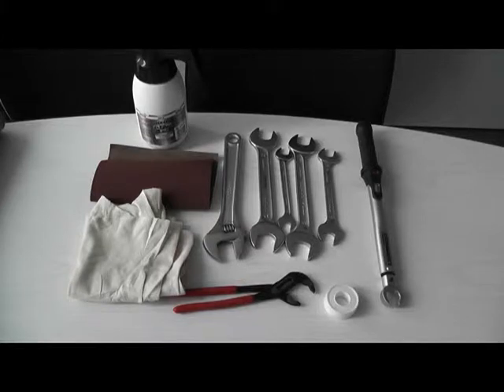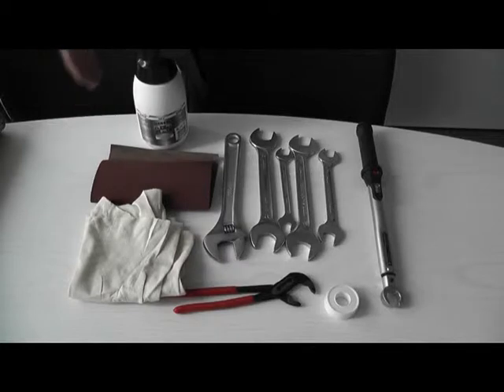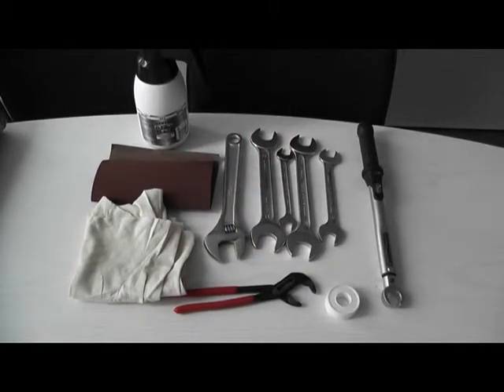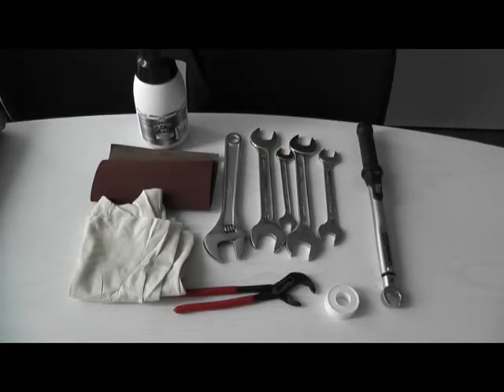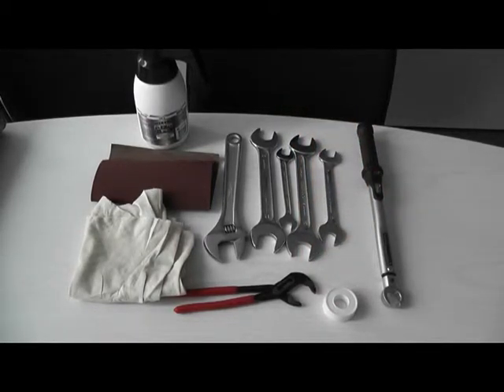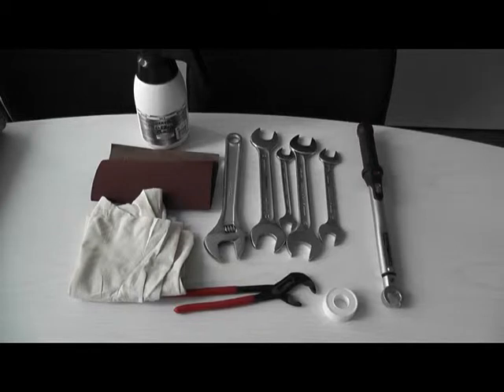To install the 6448 under pressure we also need some tools: sandpaper to remove the pipe from unevenness, a cleaner to clean the area of the pipe where the tapping clamp will be installed, pipe tongs to keep the tapping clamp in location, different wrenches to tighten the tapping clamp, ball valve and transmitter, teflon tape to seal screws, cloth to catch swarf, and a torque wrench to tighten the tapping clamp.